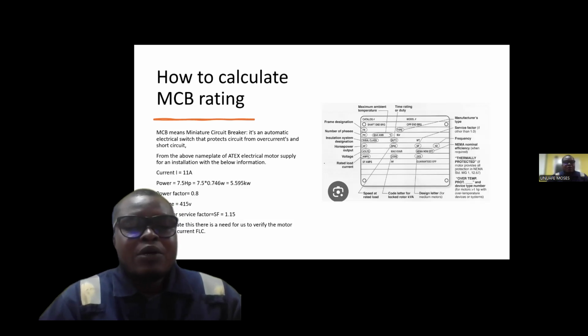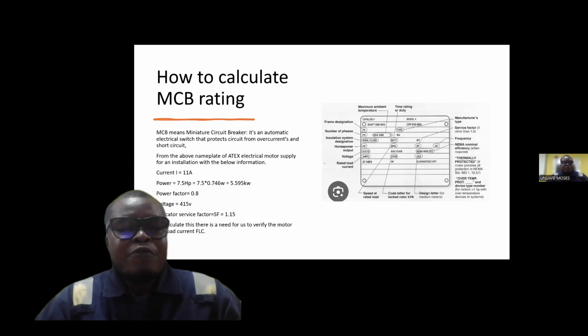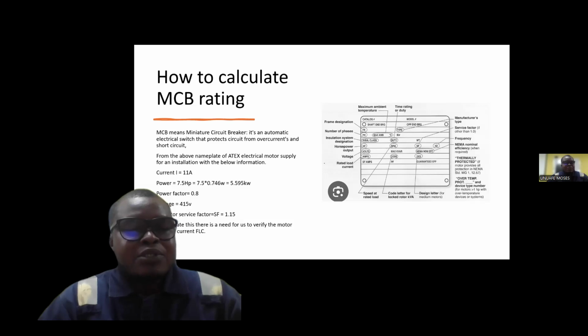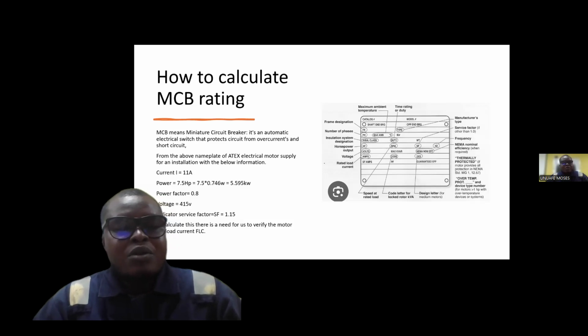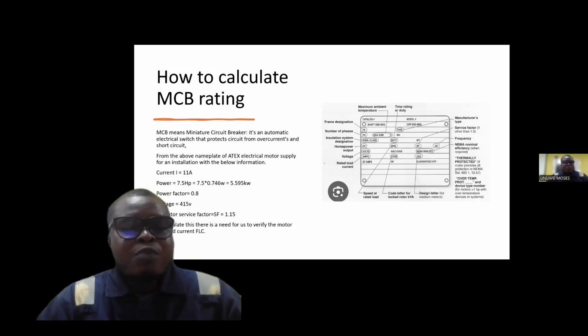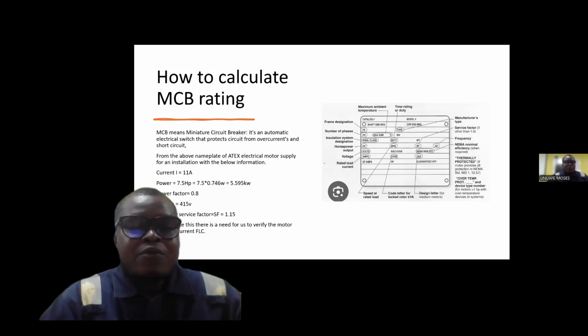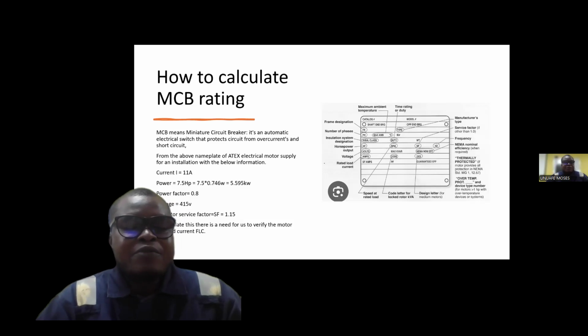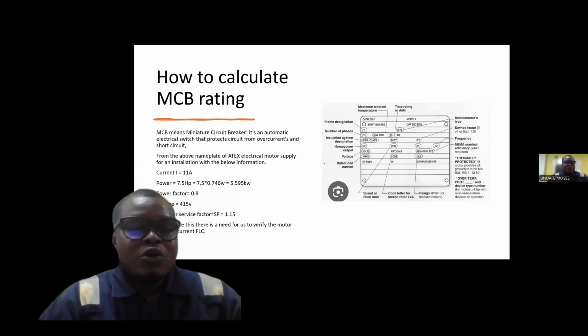From the above nameplate of the Atex electric motor supplied for installation, with the below information, which was previously on the first slide, the current on the nameplate is 11 amps, and the power is 7.5 horsepower. Know fully well that 1 horsepower is equal to 0.746 kilowatts. So when you multiply, we have 5.595 kilowatts. Then the power factor from that nameplate, we have 0.8 power factor. Then the voltage rating is 415 volts, meaning it's 3-phase.